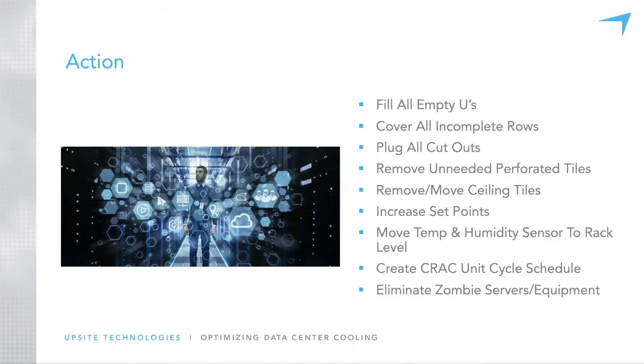So I had to be able to show and quantify that there was a difference. I started measuring, doing square inches into square feet. That first data center floor plan I showed you, people understood this. Same thing, do we really need to spend money on that? Well, you have a 497 square foot hole in your floor. They understood that. So yes, those things are not expensive, and the return on them is very significant. You cannot achieve significant efficiency and power usage effectiveness in your data center if you are leaking air. Those items are the low-hanging fruit and the place you have to start.